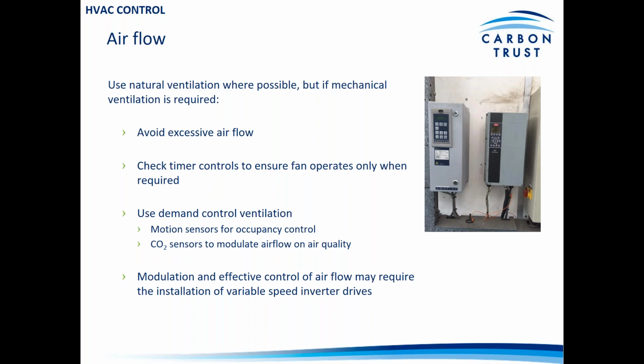Typically in fresh outdoor air, you'll see CO2 levels of maybe 400 parts per million. Indoors in a comfortable space, that might be 700 parts per million, but as that increases, it'll become increasingly stuffy. The risk though from an energy perspective is that you overly ventilate and you're providing airflow beyond what is required, and by close control of that using CO2 sensing, you can get a balance and optimize your system for energy performance. And indeed, it may be the case that if you have fixed speed systems, the use of variable speed inverter drives can enable that. So we'll come on to that in the motor section.